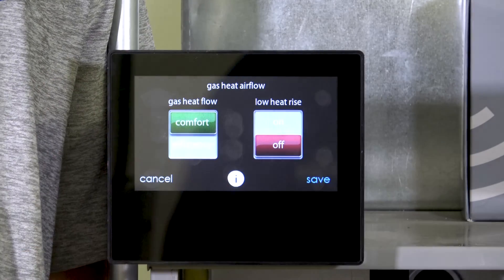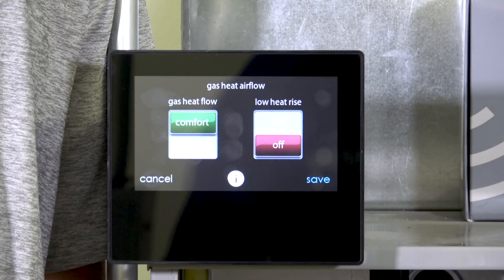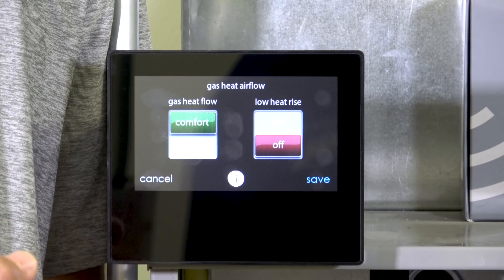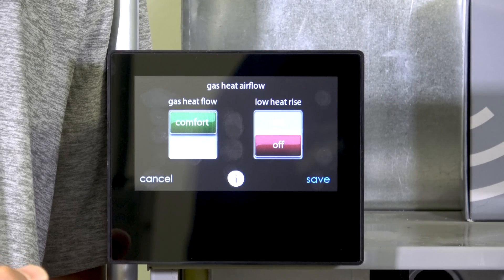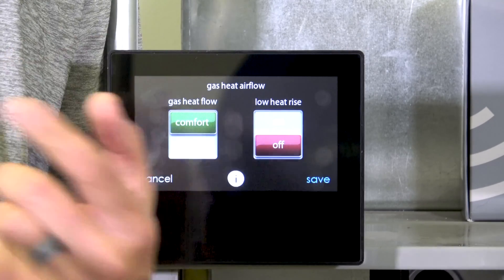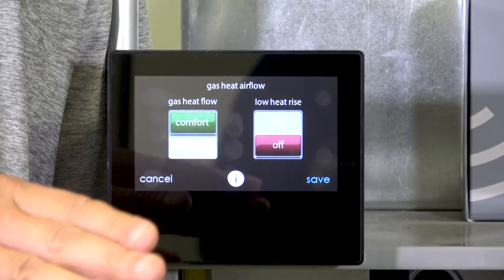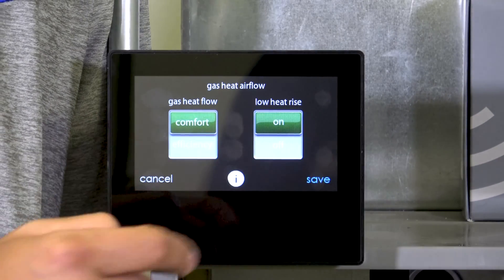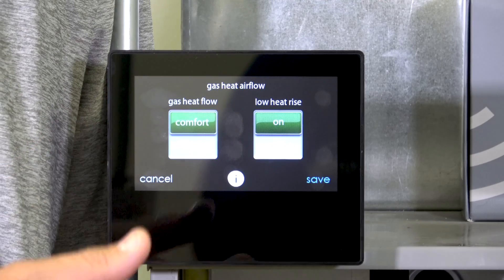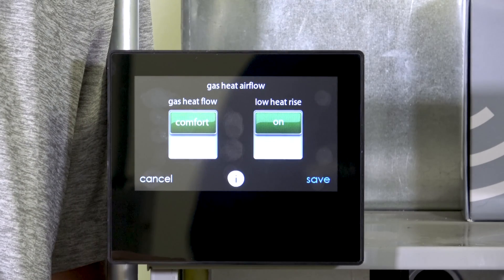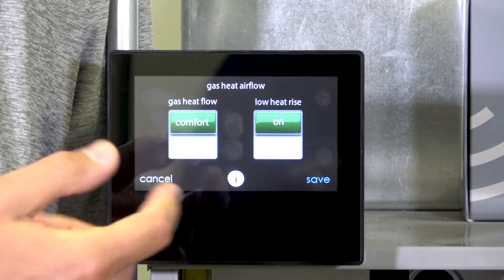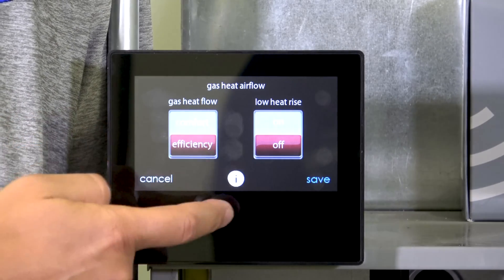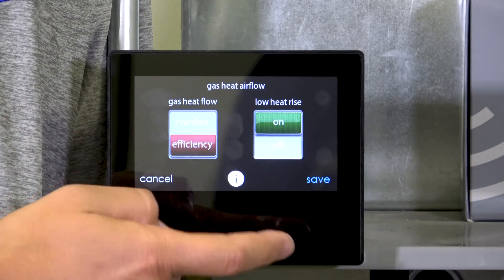Low heat rise is another heating airflow-related setting, typically for a bypass humidifier. If I have a bypass humidifier, I'm stealing some airflow off the system to run it through the humidifier, so I need to speed up the blower to compensate. So if I have a bypass humidifier I would turn that on, or if I just need more airflow in general I could also turn it on for that.